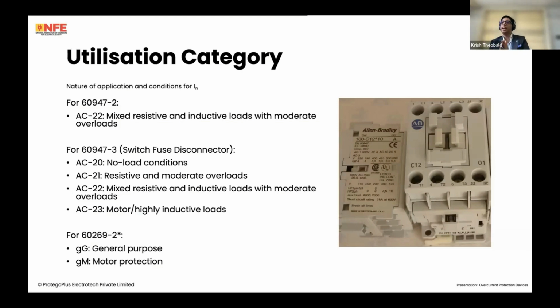So when a protected device has a certain current rating, that is your IN, these are given for these utilization categories. So for instance, if you've got a device that is normally rated under AC20 for say 63 amps, but you're actually using it to switch motors and highly inductive loads, you cannot use that. This is a different rating, say 10 amps. You have to use a 10 amp rating. So you have to choose the IN value. You can see these are provided on your actual protected device or switching device. You have to choose the IN value depending on the utilization category.